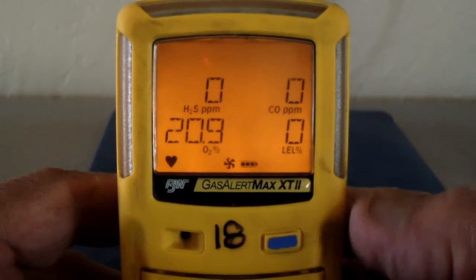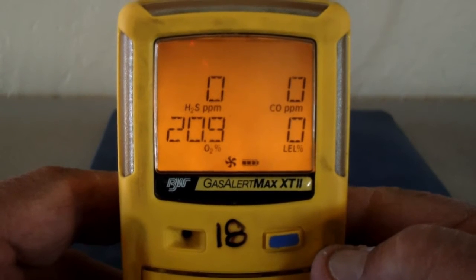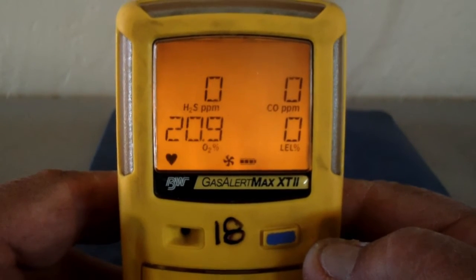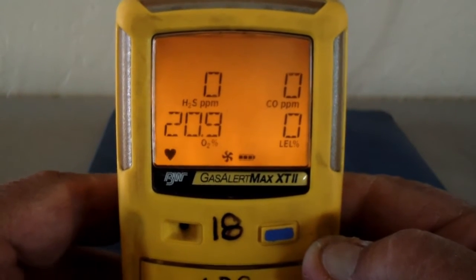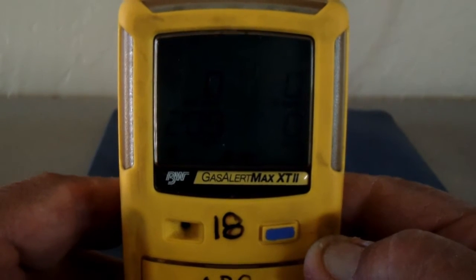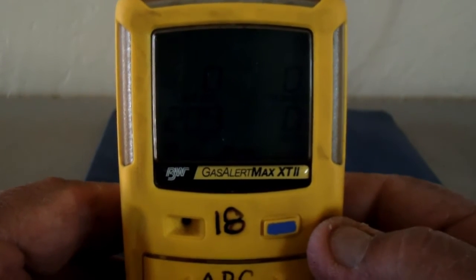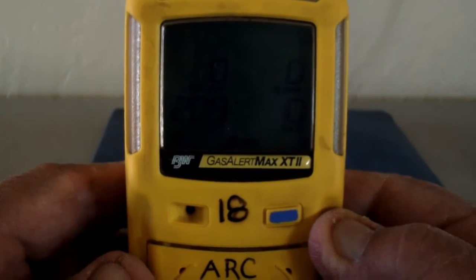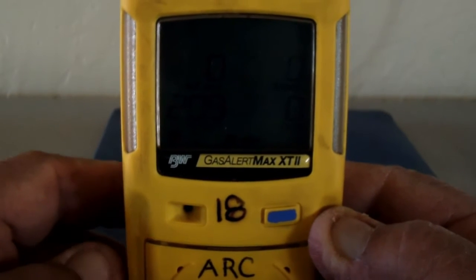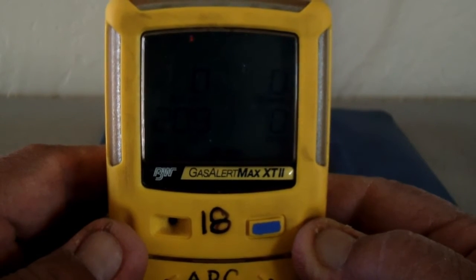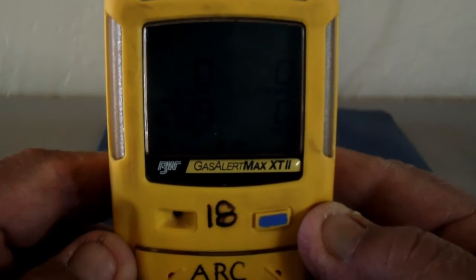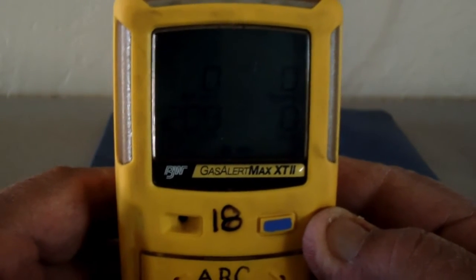These meters come from the factory set up for 180-day calibration. We calibrate this machine monthly, actually sometimes far greater than monthly. Whenever it requires it, we will calibrate this machine. We also bump test these machines daily before use. According to the manufacturer of the sensors, the only way to make sure that this machine is working properly is to bump test it. And I'm going to go ahead and do a bump test now.